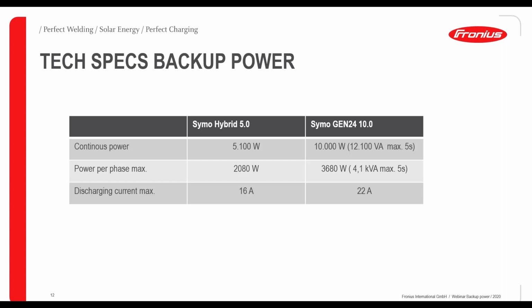Yes, this is actually the basic points. Then what about the continuous power in backup power mode? On the Symo Hybrid 5 we can offer 5.1 kilowatt. With the Symo Gen24 10 we can offer 10 kilowatt. Maximum here is 12 kilowatt, but for maximum 5 seconds. Then power per phase, a bit more than 2 kilowatt on the Symo Hybrid 5 and 3.68 kilowatt on the Symo Gen24. So we have higher power per phase as well. And the discharging current is also different, 16 amps for the Symo Hybrid and 22 amps for the Symo Gen24 10 kilowatt.